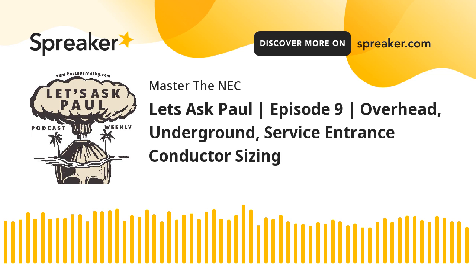So this might be where you have current-carrying conductors that exceed 3, so 4 or more. Or this might be where your conductors are installed in a location with an elevated ambient temperature that's higher than 30 degrees Celsius and 86 degrees Fahrenheit.